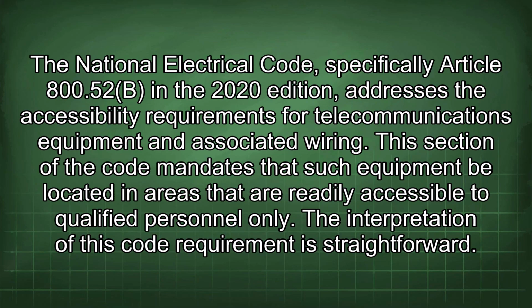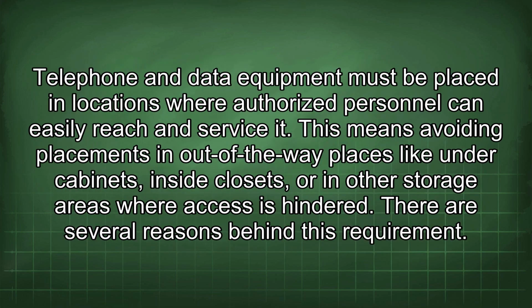The National Electrical Code, specifically Article 800.52b in the 2020 edition, addresses accessibility requirements for telecommunications equipment and associated wiring. This section of the code mandates that such equipment be located in areas that are readily accessible to qualified personnel only. The interpretation of this code requirement is straightforward. Telephone and data equipment must be placed in locations where authorized personnel can easily reach and service it. This means avoiding placements in out-of-the-way places like under cabinets, inside closets, or in other storage areas where access is hindered. There are several reasons behind this requirement.